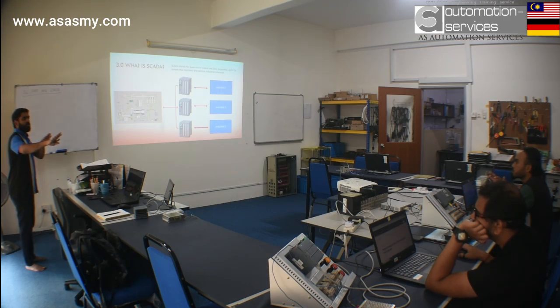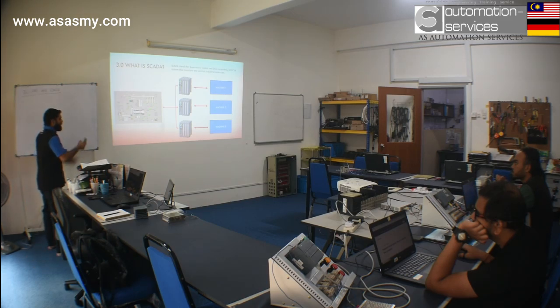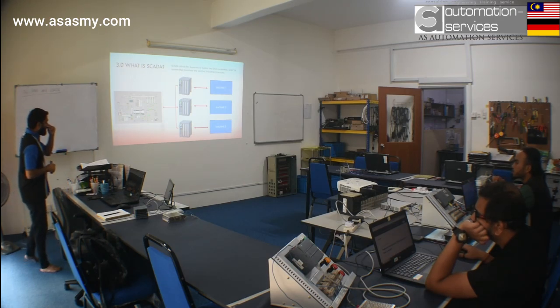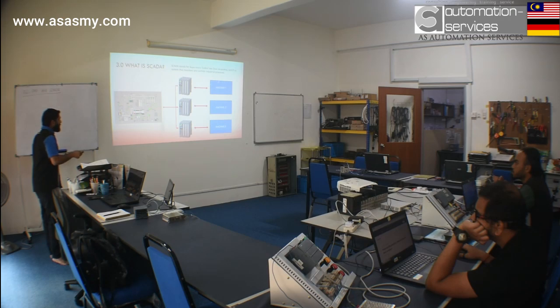It's similar to HMI. HMI mostly has the controls for the particular machine only, yes, for one machine. But SCADA means mostly it can control all three machines together, but mostly they don't do control, mostly what they do is collect the data. That's the idea of SCADA, because they want to know the behavior of your machines. But from where do they take it?